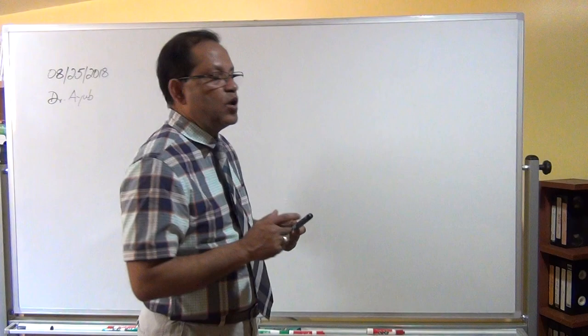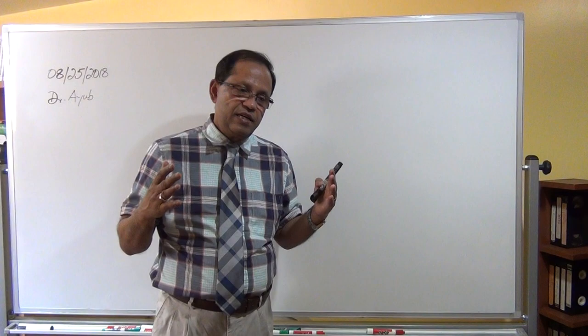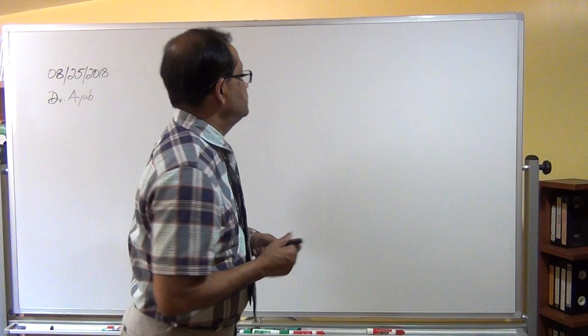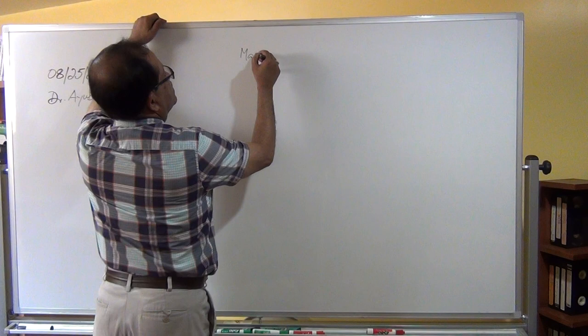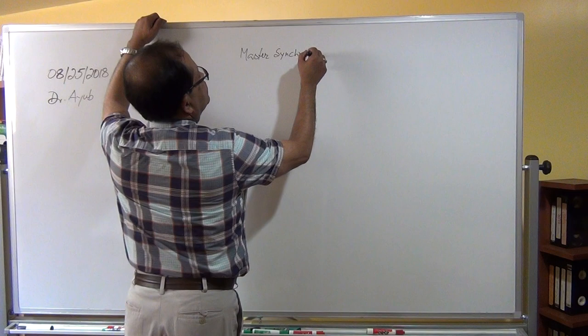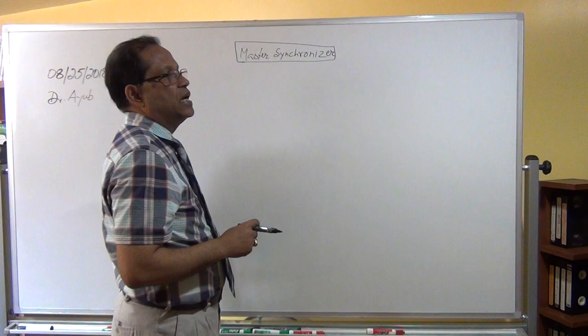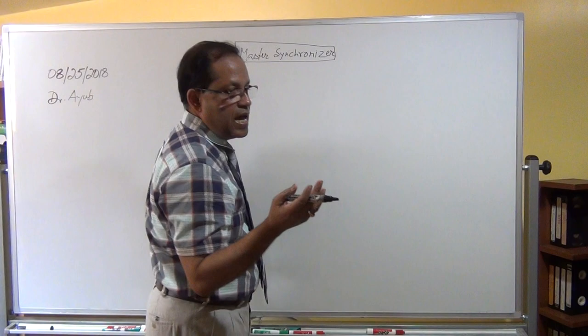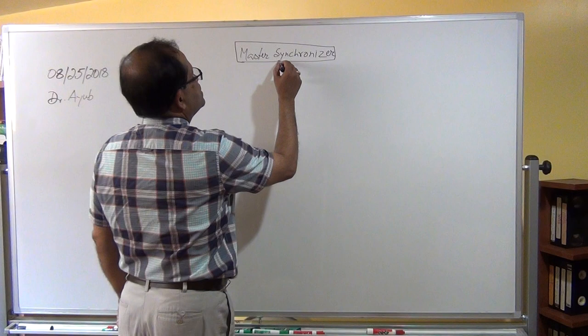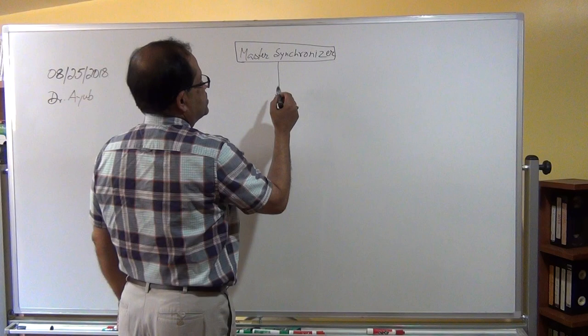Let me give you a couple of drawings to help you better understand how the ultrasonography machine works. You have to understand that there is a button called the master synchronizer. The master synchronizer is the master mind — the main controlling structure — and you can consider it as the brain of the machine. This master synchronizer oversees all the component parts and gives signals to the pulser.